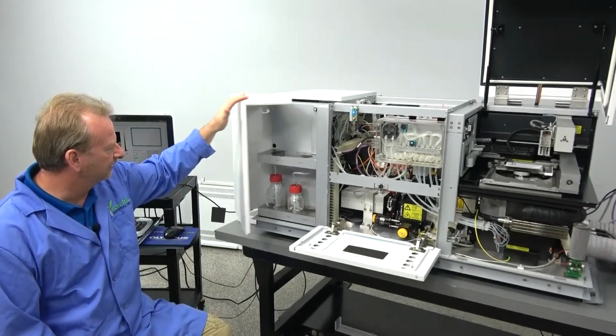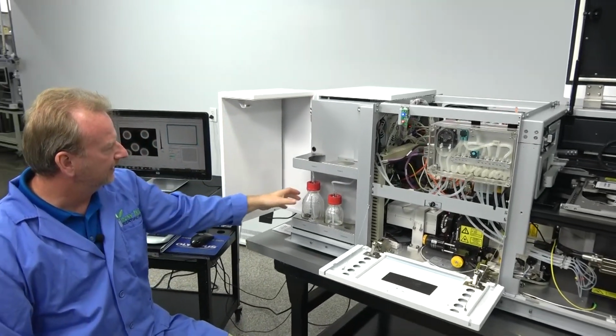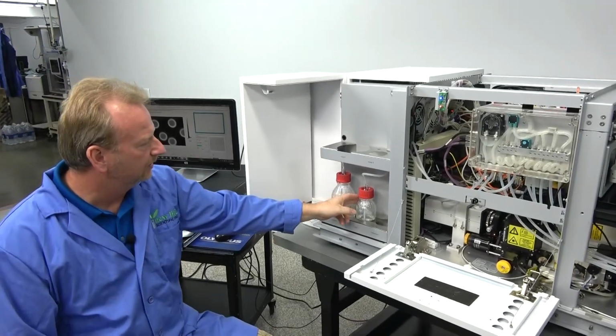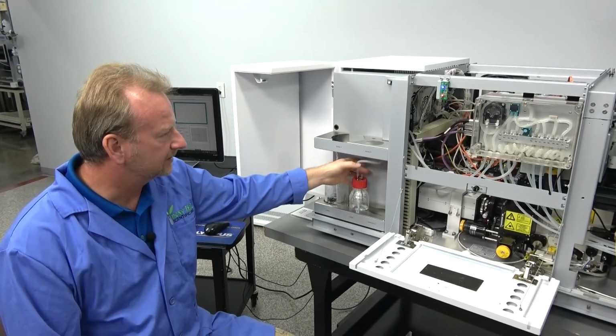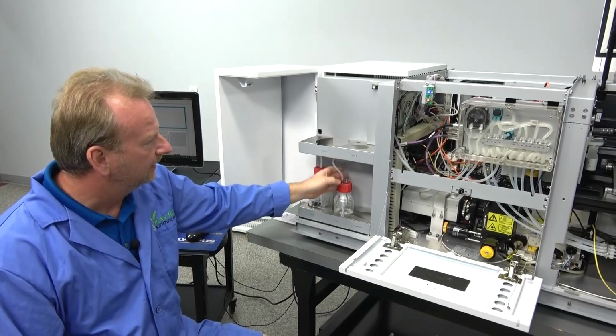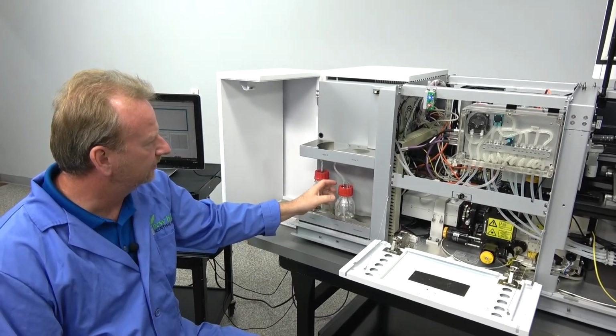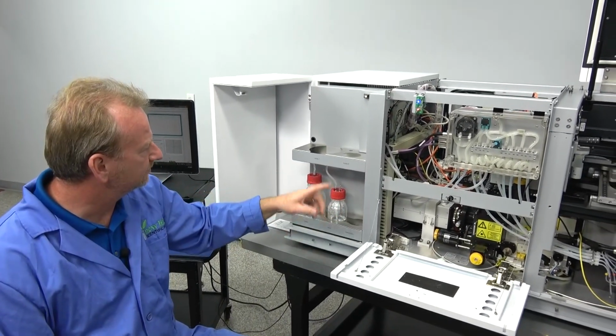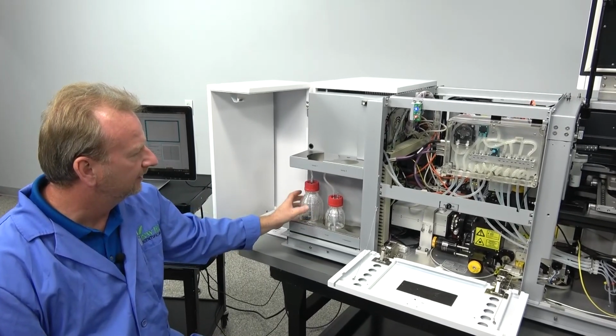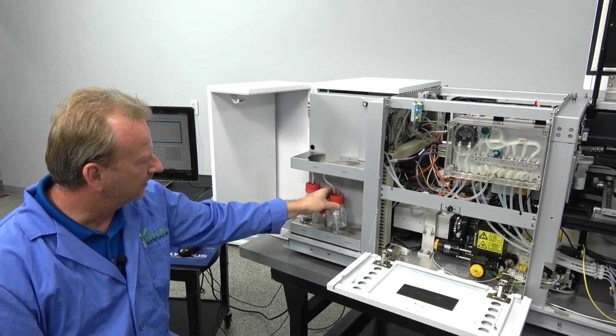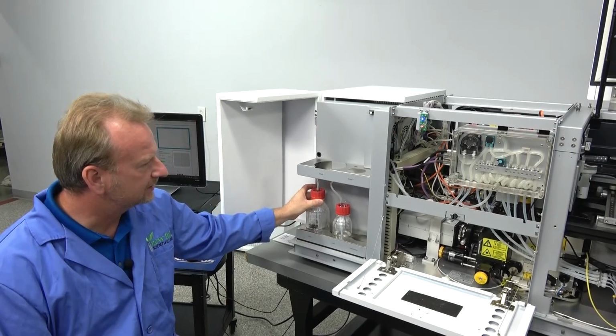This is simply a door that opens here, containing your waste bottle and your wash fluid, which is basically purified water. It pumps it from this bottle up into the immersion lenses and brings the waste back down here. So you just need to always make sure you have water in here and dump your waste.